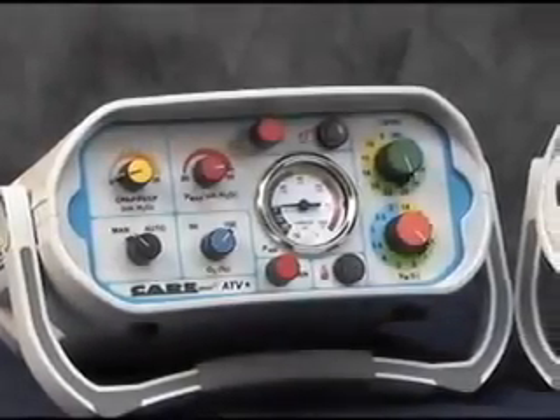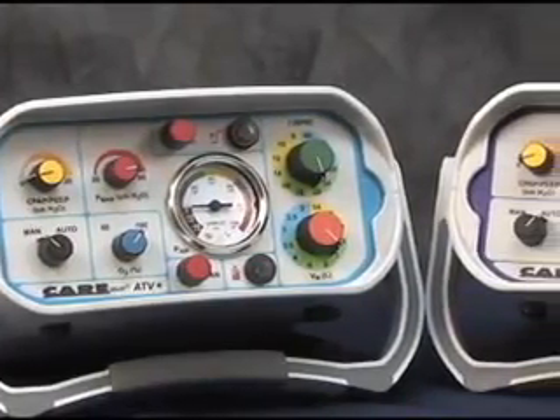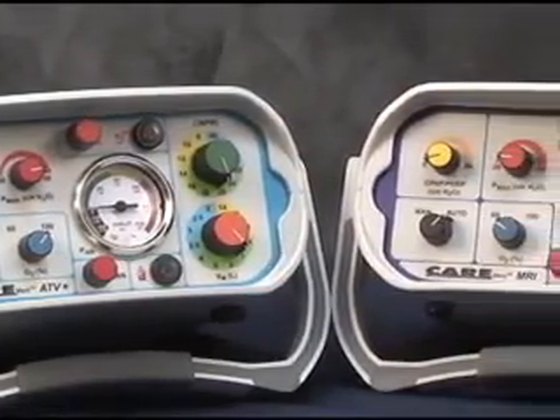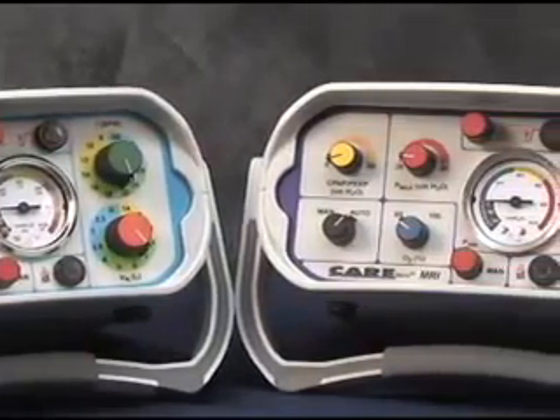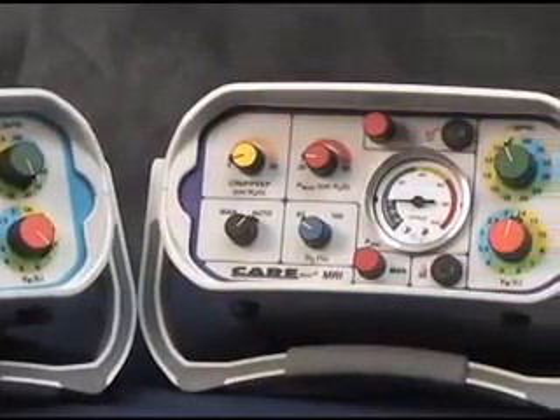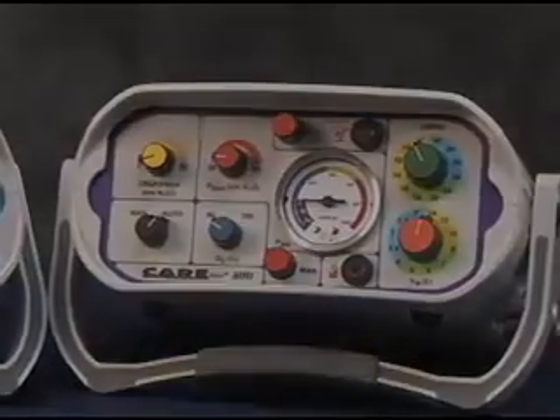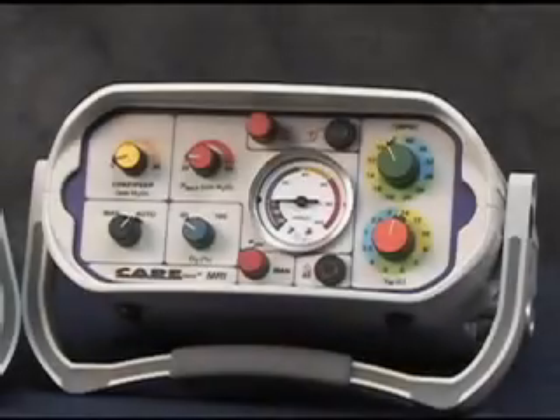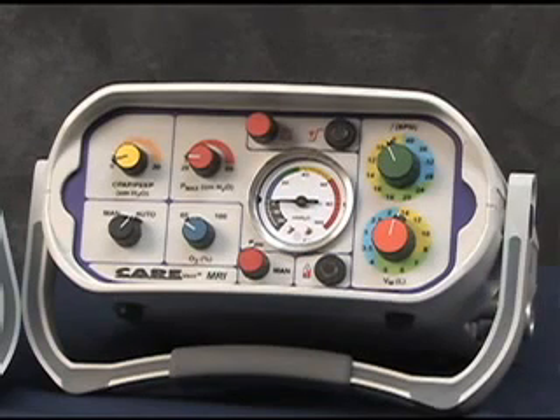The CAREvent ATV Plus and MRI have been developed to meet the challenges of transport and resuscitation of the respiratory impaired patient by providing a wide range of ventilation parameters in a totally pneumatically powered, compact unit. The removal of all ferrous metal components from the ATV Plus to provide the magnetic resonance imaging compatible feature of the CAREvent MRI allows this device to be used in MRI environments up to 3 Tesla, with no effect on either ventilator function or scan quality, even with the ventilator positioned next to the magnet.